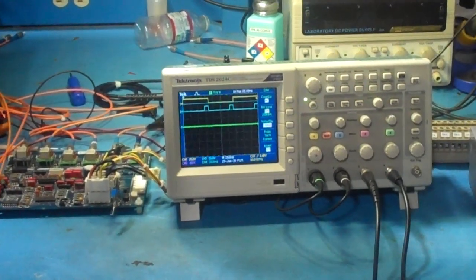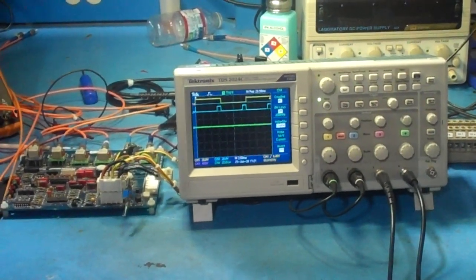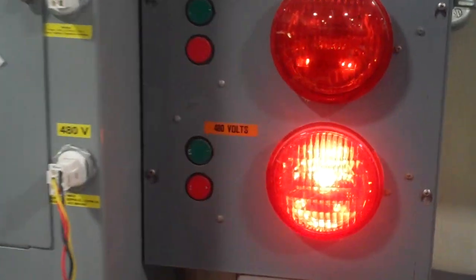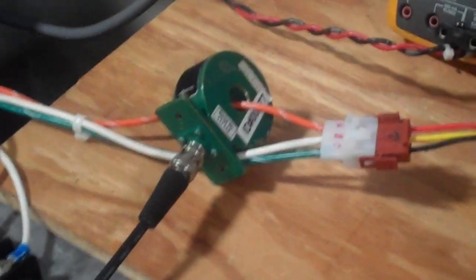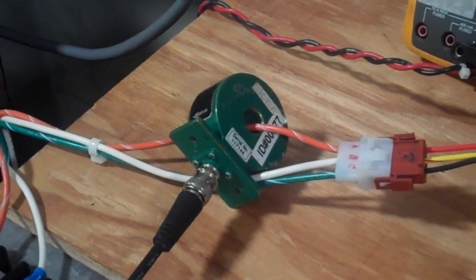Today it's Monday, June the 29th, 2026, and what we have here is a three-phase AC controller, three dual SCR, A, B, and C, and we have it fed from 480 volts from our wall, and we are monitoring with a CT the current out of the AC, from the A line, and then we're monitoring our output with a differential between A and B, the 0 to 480 volts, and we also have here our multimeter.